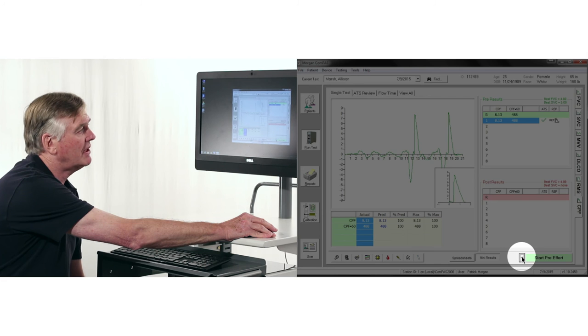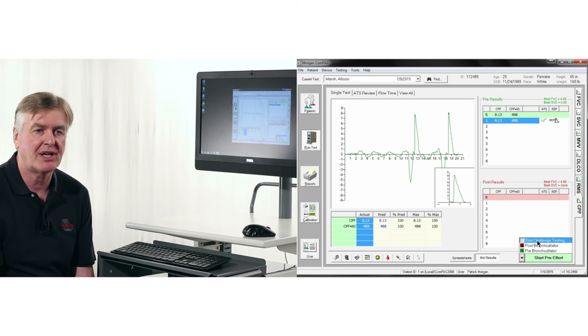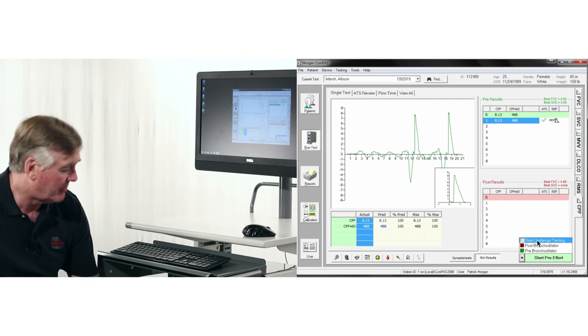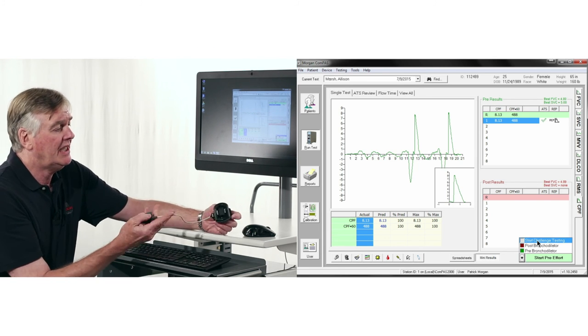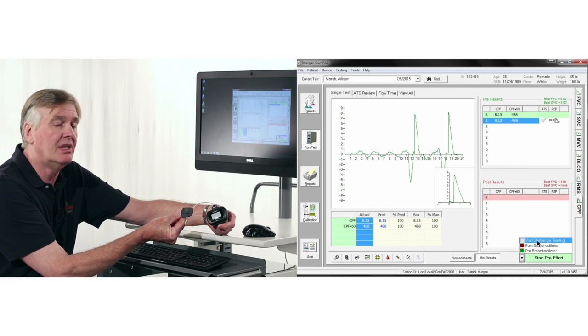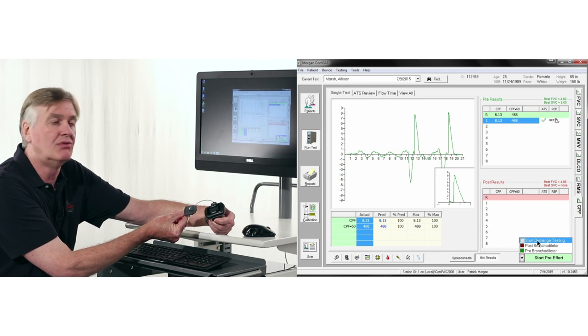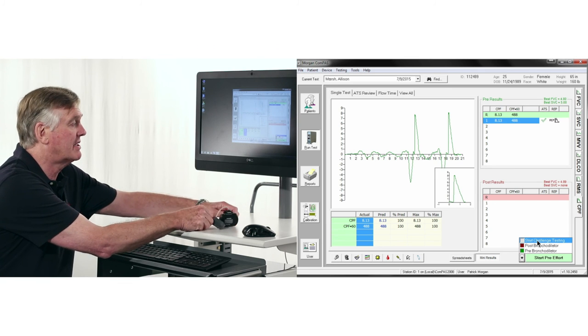The instrument is also capable of doing challenge testing. The challenge testing can be cold air, it can be methacholine or aridol, any challenge test sequence that you want to do. A further option with this instrument can be added by using the Nonin WristOx. So with this particular device, you could also add 6-minute walk into your reporting. It's very simple to use. You can gather the resting, the 6-minute walk, and the recovery data, and it's automatically read into the ComPAS software so that it's very easy to add 6-minute walk to any practice.